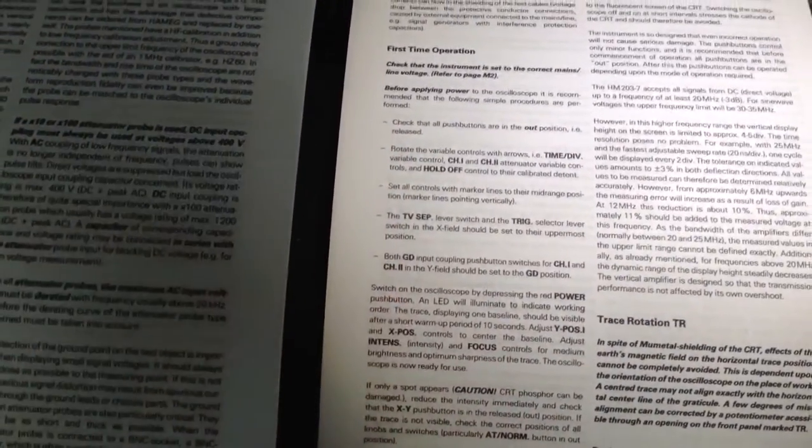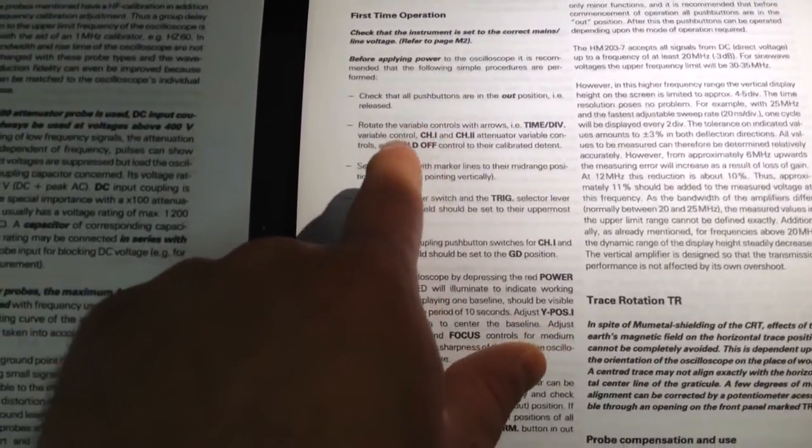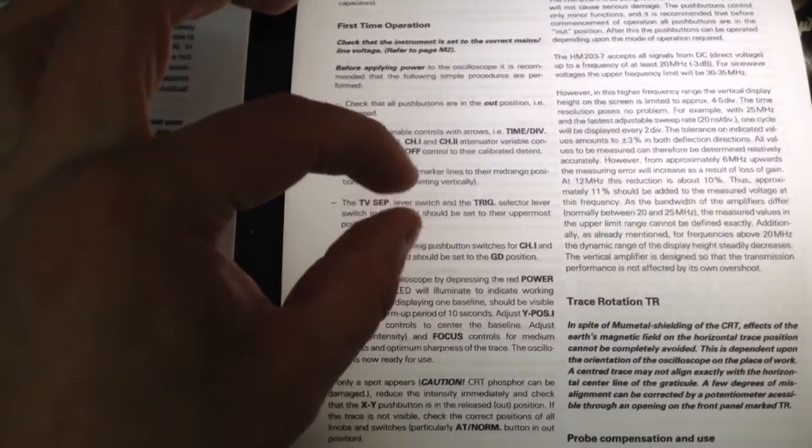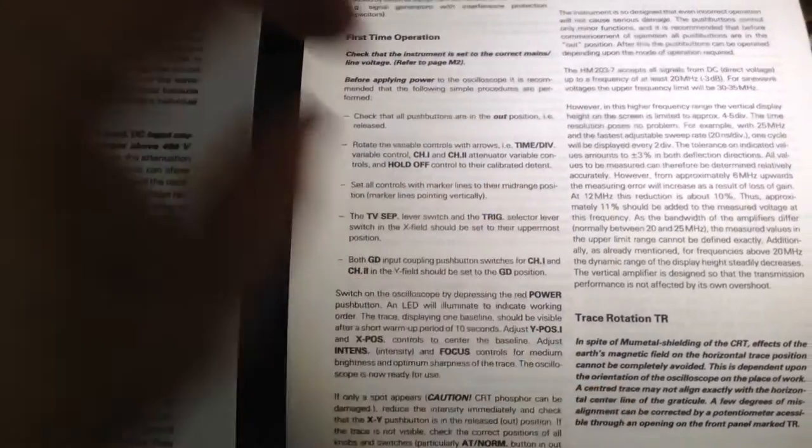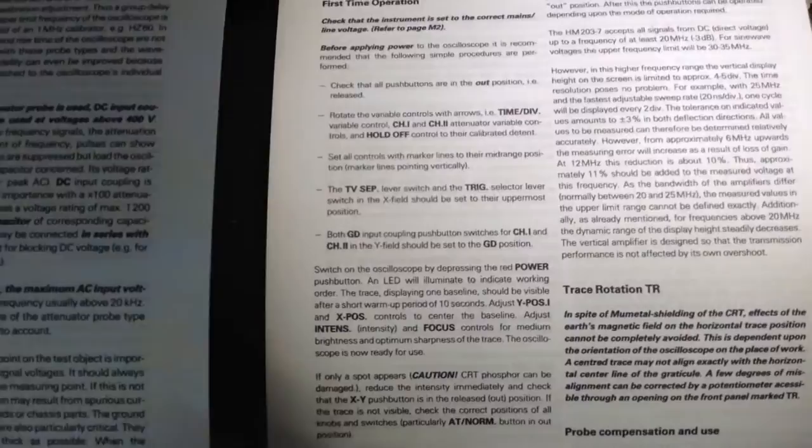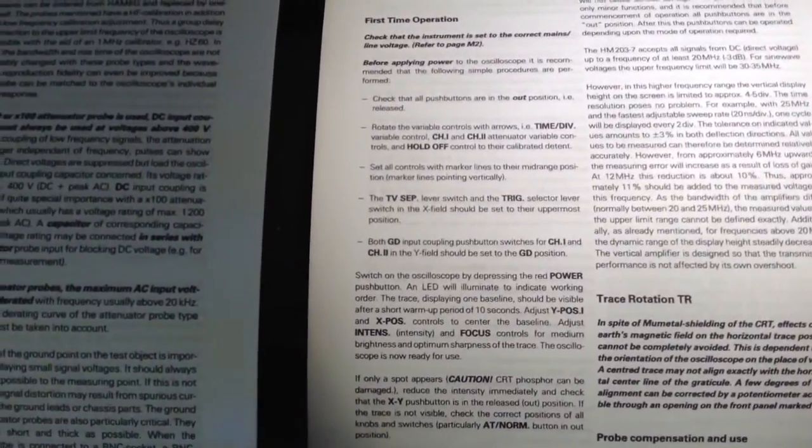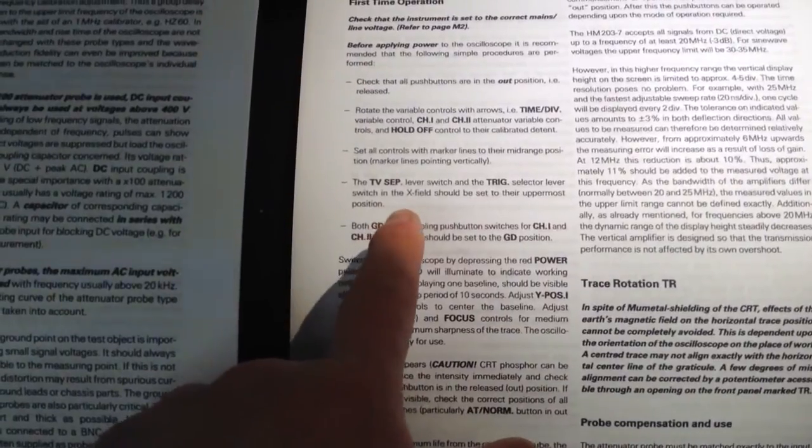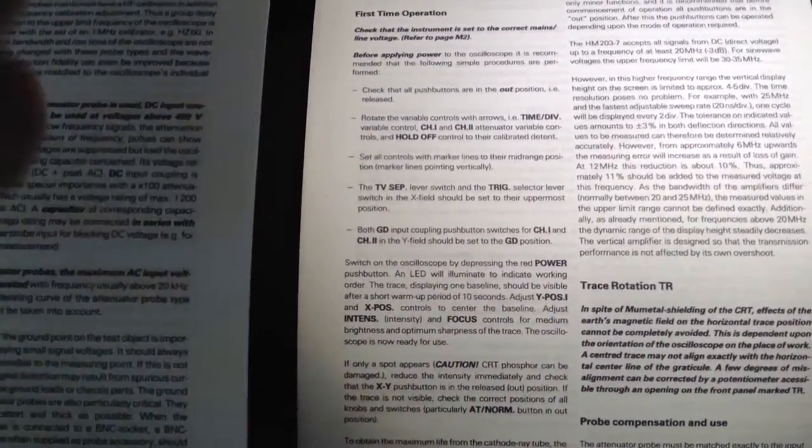Basically just to check to make sure when you turn it on you can see a trace. Check that all the push buttons are out, rotate all the variable controls with arrows to their detents, set all the control markers to mid-range position. TV-sep and trigger selector levels all the way up, and both ground coupling switches set to ground.